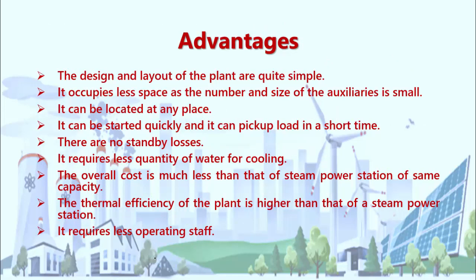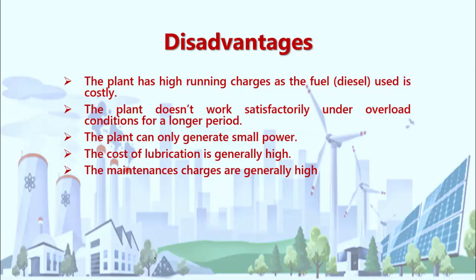Now, the advantages of diesel engine power plants are that these are all quite simple, and they occupy very little place and can be located at any place. The starting time and pickup load will be very small. There are no standby losses. It requires a smaller quantity of water for cooling when compared to other power plants like steam power plants and hydro power plants. A very negligible amount of water is required for this type of engine, right? The thermal efficiency of the plant is higher when you compare it to the steam power plant, right?